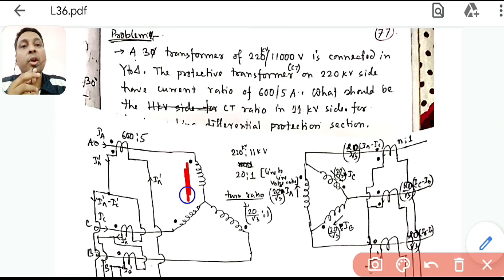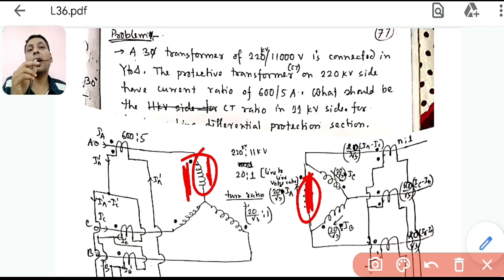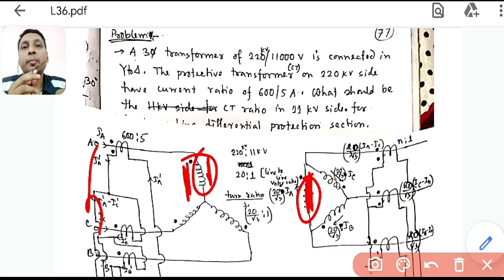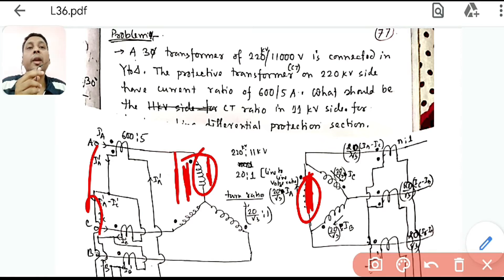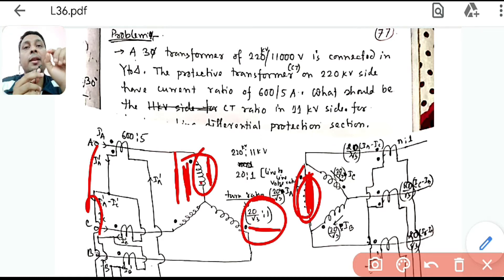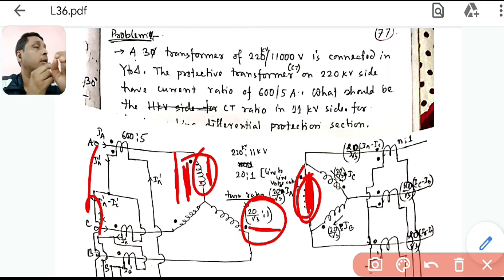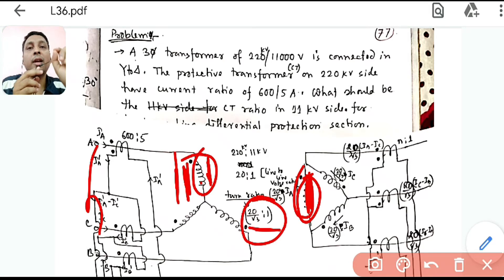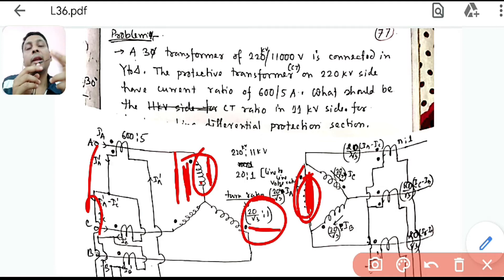To find the turns ratio, we compare phase voltages. The star side phase voltage is 220/√3 kV, and the delta side phase voltage is 11 kV. So the turns ratio is 220/√3 to 11, which is 20/√3 to 1 — not 20:1. The line current ratio is the inverse of the voltage ratio: 1:20.